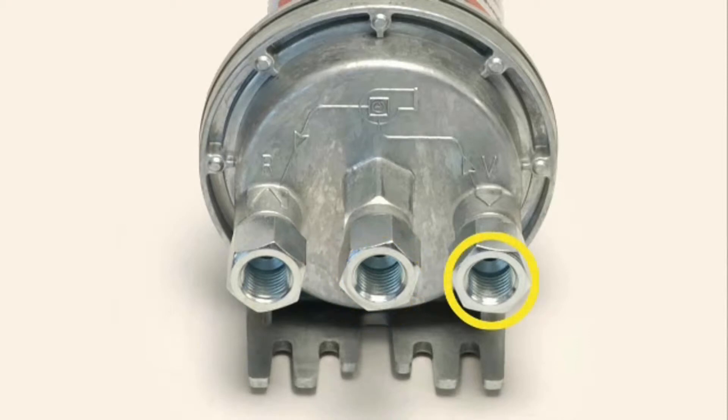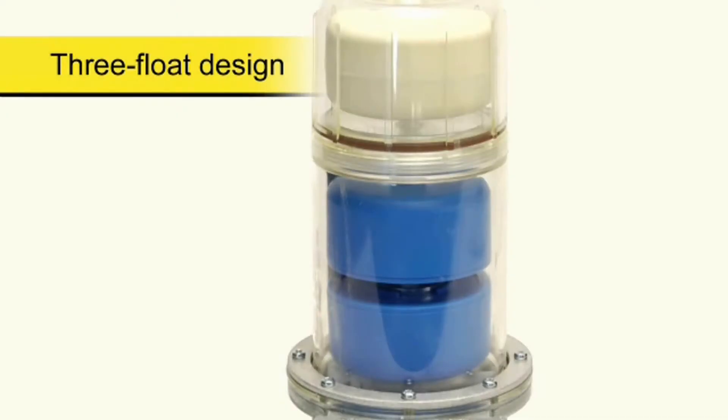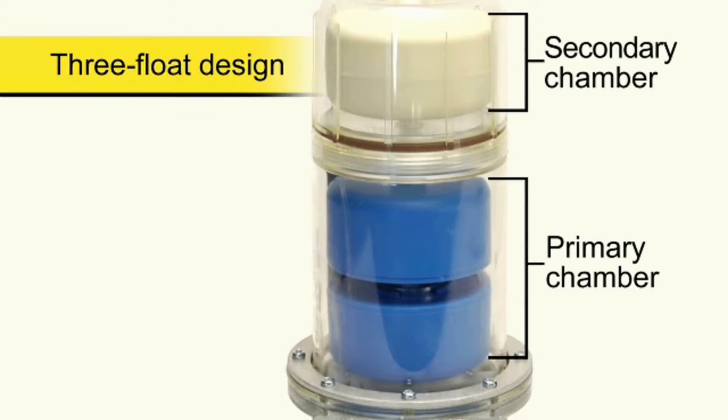A big advantage of our deaerator is its three-float design. There's a primary chamber with two floats, the deaerating chamber. A secondary chamber is designed to prevent any foam from escaping if the deaerator becomes over-aerated or over-foamed.